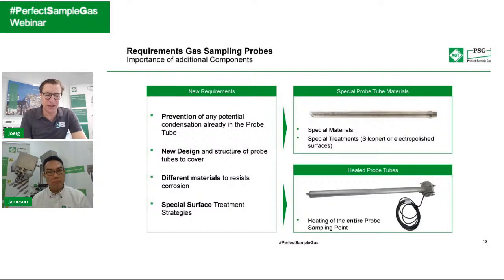Sometimes, James, I think our audience is maybe listening to this often enough, or knows this from the background. It's a very common question: why do we need that 150 or even 180 degrees? Because in some stacks, especially if there is an FGD, flue gas desulfurization, whereby they use caustic or some kind of limestone or water or even seawater to wash the sample, there is also dust, there are particulates, and now the sample becomes lower than the water dew point. The temperature is very low, and the particulates are also sticky because they are dust.